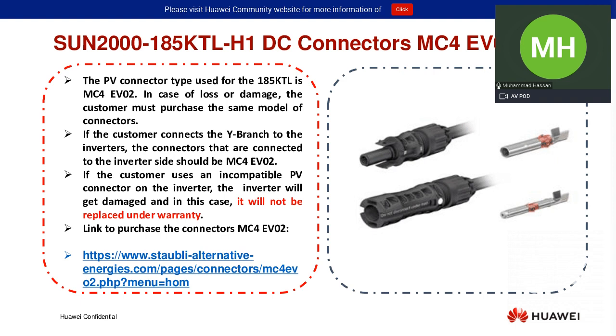You can also use branch connectors to connect the MC4, which are locally available in the market. And if you use incompatible PV connectors on the inverters, the DC input side could be damaged, and in that case, as I mentioned before, we are not replacing the product under warranty.